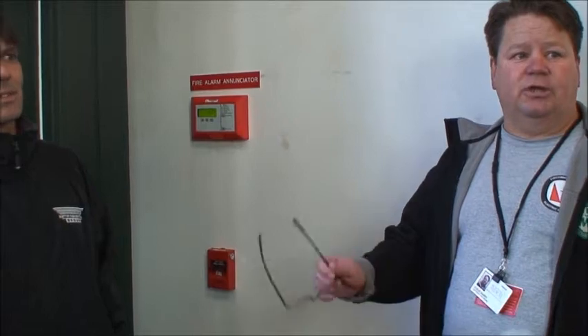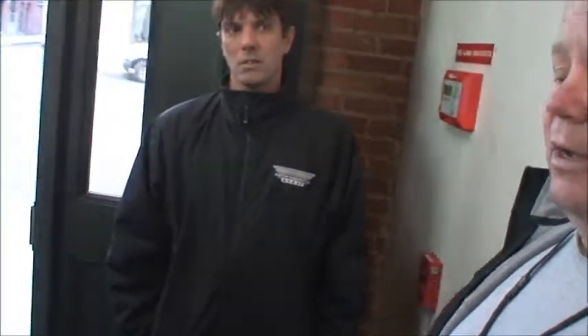Even inside the unit, if someone sets off their smoke detector, the smoke detectors in the unit are not hardwired to the system. They're hardwired to each other, but they do not leave the apartments. The only things inside the apartment connected to the fire alarm panel or system are their strobes, the speakers, the horn strobes. Those will go off from any alarm in the building outside of somebody's apartment.